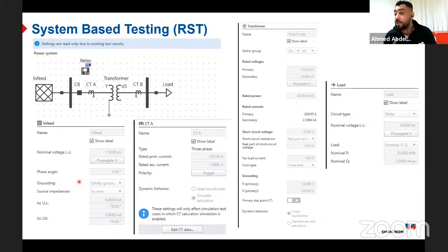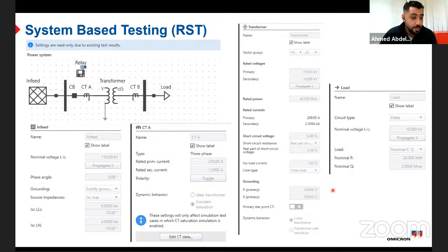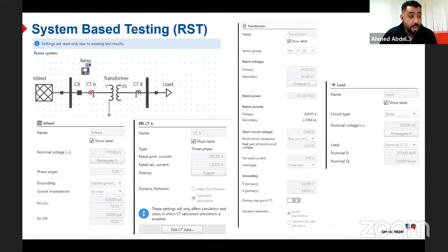I need to draw the in-feed. As you can see, I need to draw the in-feed. I need to draw the transformer. I need to draw the current transformers, CT A, CT B, and also I need to draw the load. This is very, very easy. I will define the in-feed based on my system. I'm pretty sure that every protection engineering department has the short circuit data, the nominal voltage, the short circuit impedance, everything about the in-feed. The transformer data you can get from the nameplate of the transformer.